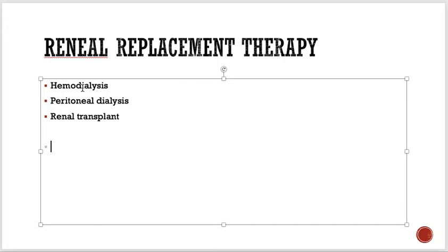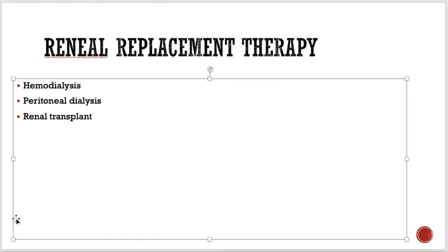the basis is the same. The blood passes through a semi-permeable membrane, and there is a dialysate fluid running on the other side, where there is basically an exchange of things. And the dialysate, of course, they prepare it especially to make the blood lose all its nitrogenous waste, creatinine and urea, and the extra electrolytes and the extra volume.